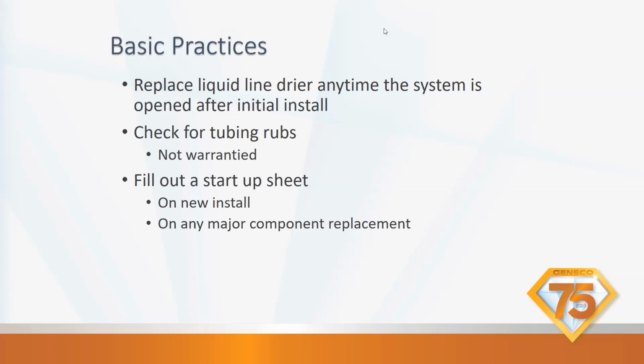They're putting heat shrink on a lot of the tubing now so that they don't rub. But remember, it gets put on and off a truck several times before it gets to us. So make sure that you're checking for tubing rubs, for loose wires, loose set screws on blower wheels, on fans, all that kind of stuff. Anything that can get loosened by vibration and traveling, you should be checking on install, and you should be checking it on your service calls, on your maintenances.